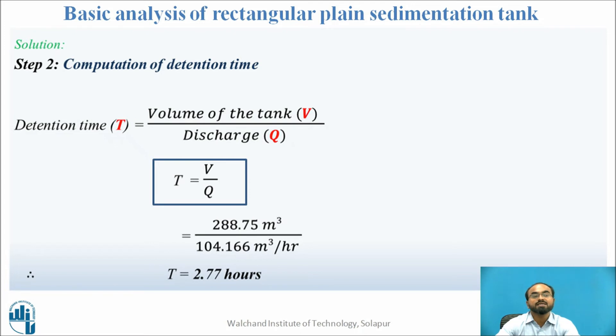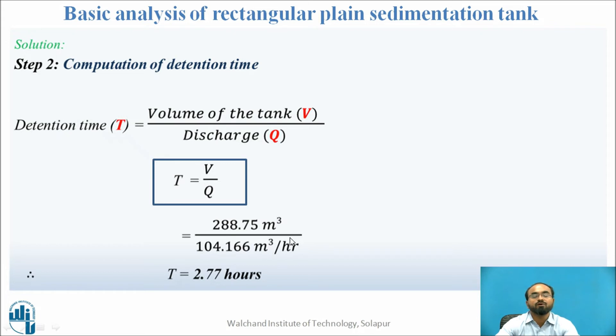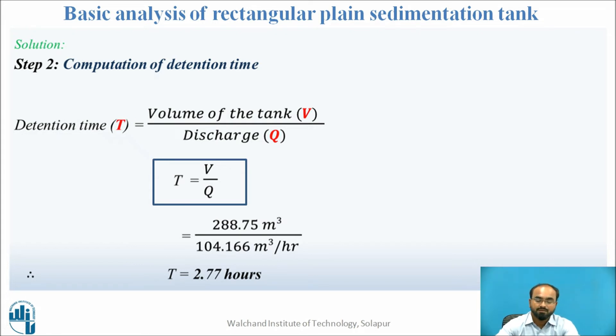Second, detention time: T = V / Q = 288.75 m³ / 104.166 m³ per hour = 2.77 hours. This is the detention time of the sedimentation tank.